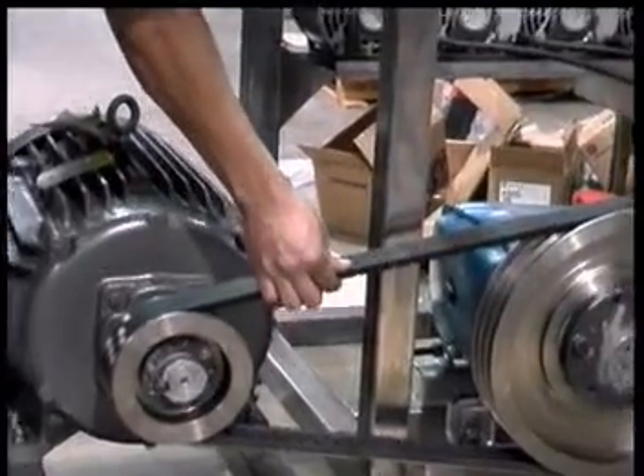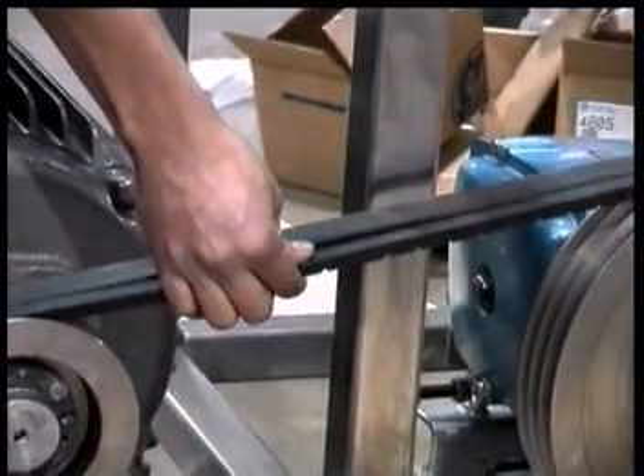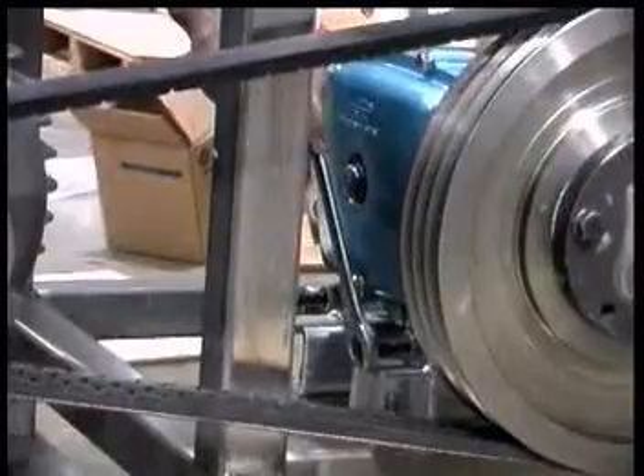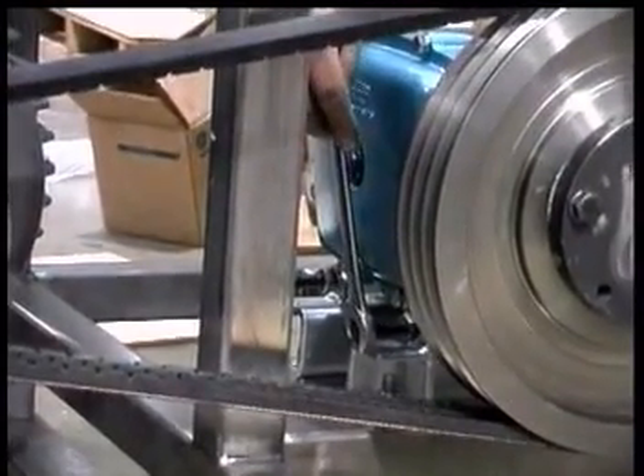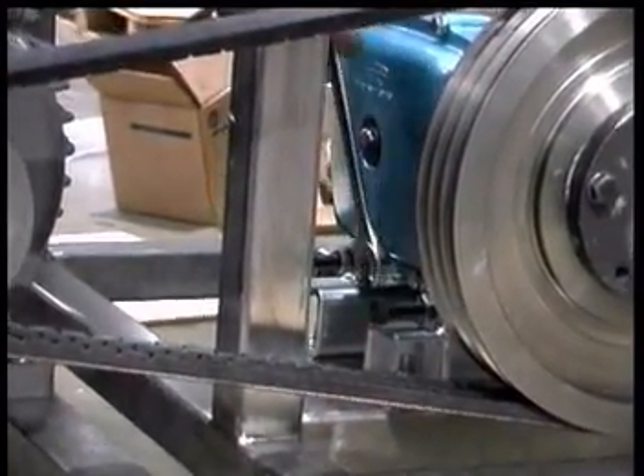The belts should be kept tight enough so that they have half-inch movement to either side of their normal resting position. Adjustment is made with the adjustment screws located on the bottom side of the pump.